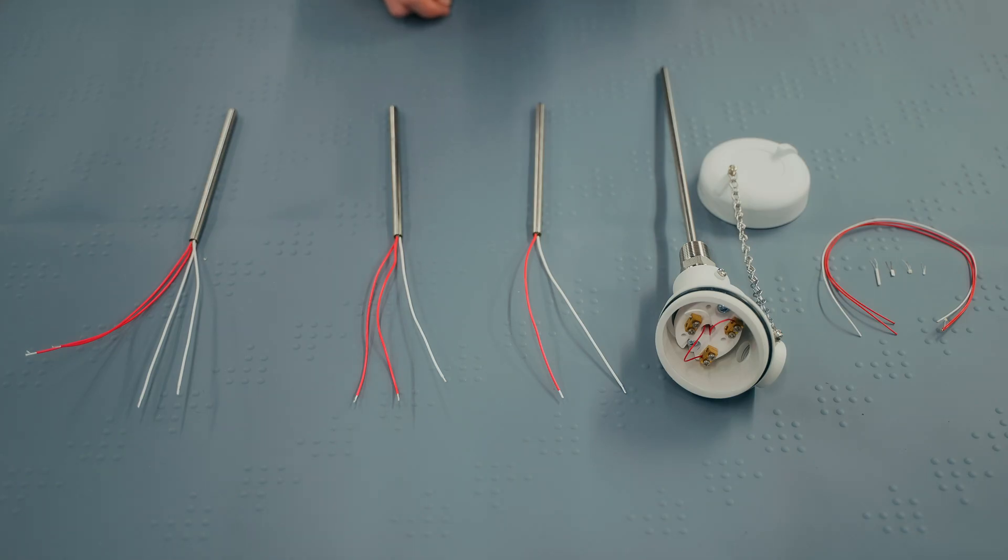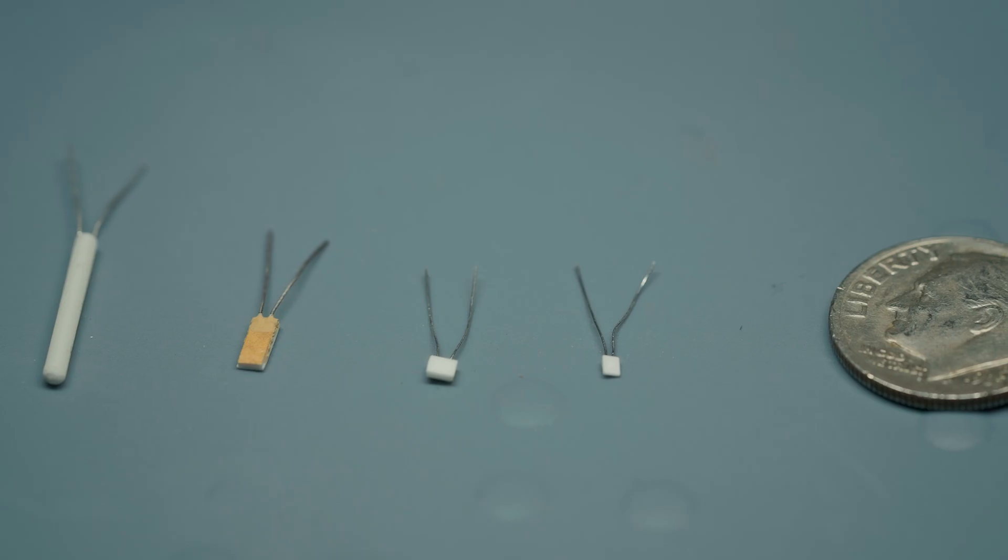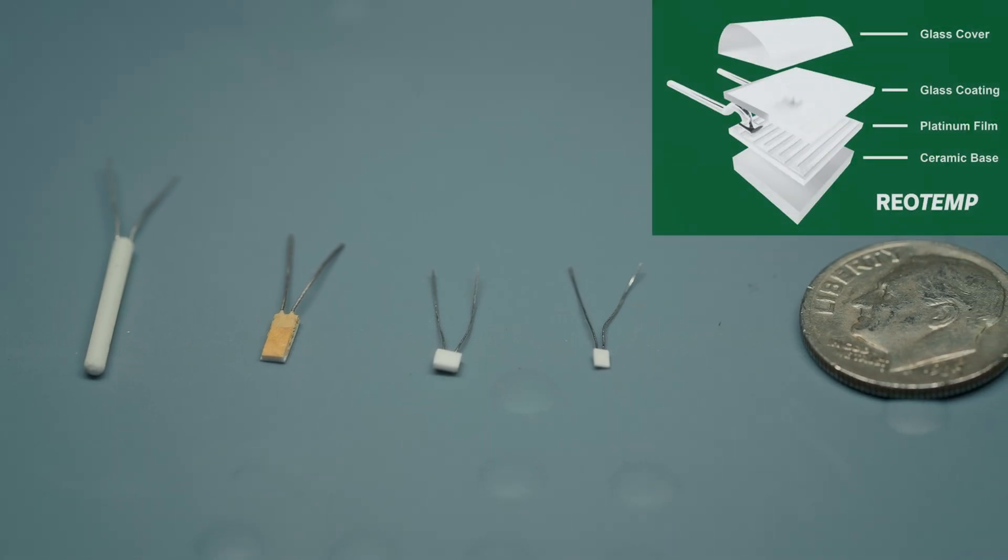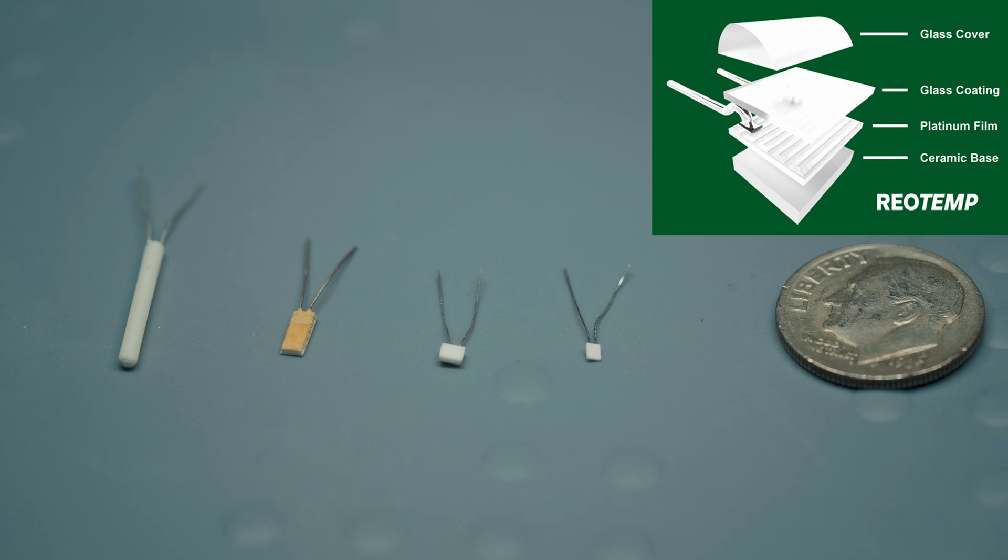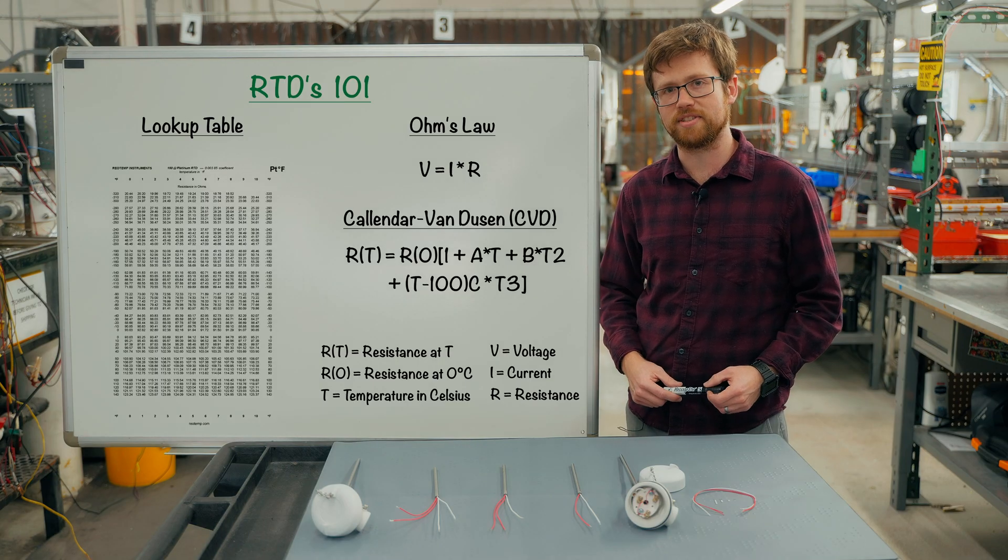RTDs come in many different shapes and sizes but are most commonly constructed as thin film elements. A thin layer of platinum is etched onto a ceramic base and covered in protective glass. As the platinum heats up, its resistance increases.